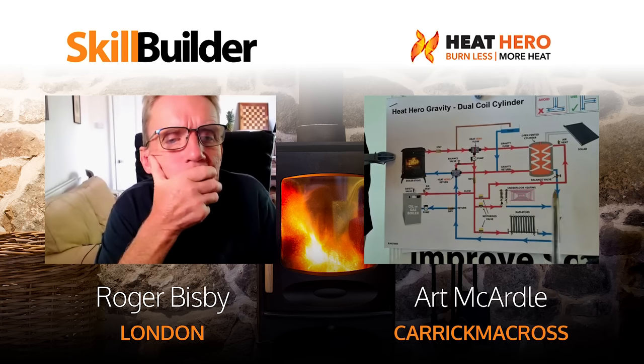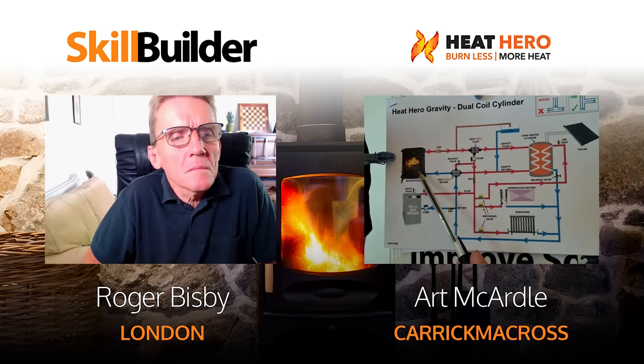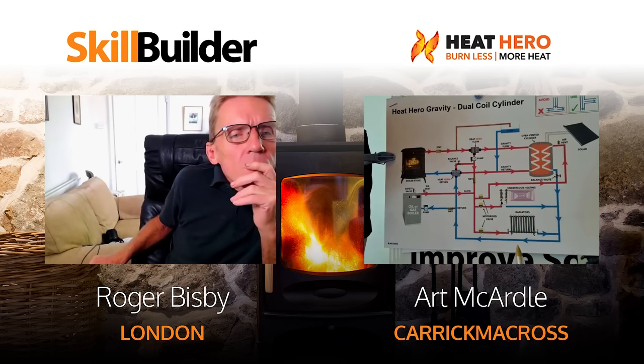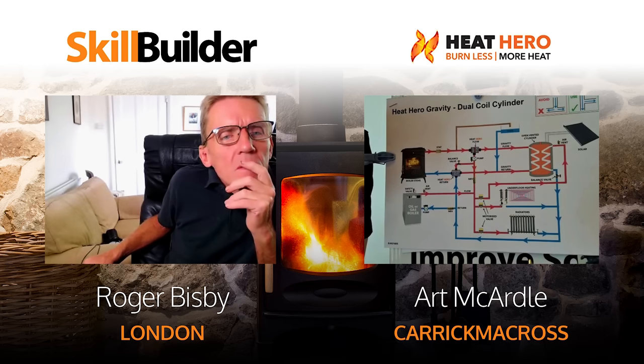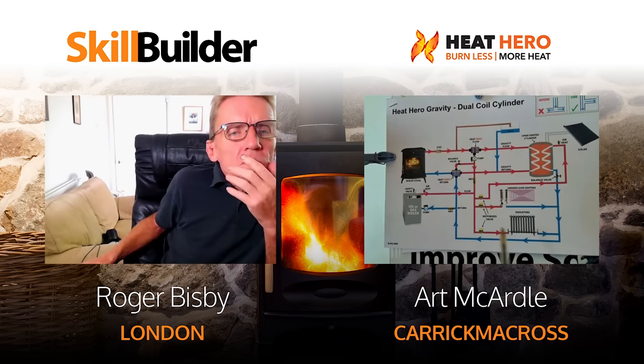We realise that solid fuel is non-controllable. The most important thing about solid fuel, apart from safety, is circulation. If you don't get the water through that stove fast enough, that fuel has gone up the chimney. It's not like an oil or gas boiler that will turn off and wait on the pump to take away the heat - solid fuel won't turn off. So we're now recommending all solid fuel heating systems be fitted with 8-metre circulating pumps. We stop at 8 metres because that's the largest residential pump available within a reasonable price range.